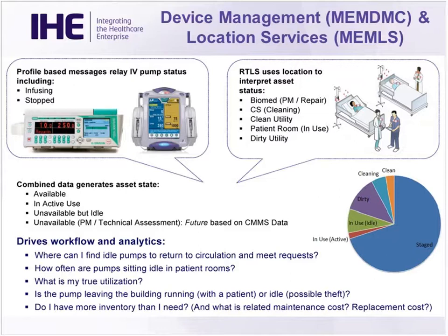But the idea there is that the devices can produce observations that are not necessarily patient-related, they're equipment management-related. So we have a means of communicating that. Also, the equipment management information can be used in conjunction with other profiles, such as the DEC or ACM profiles. So it allows for things like the identification of the equipment, the last power fail status of the equipment, the power source, be it mains or battery, battery status, battery charging status. That information can be communicated by MEMDMC.